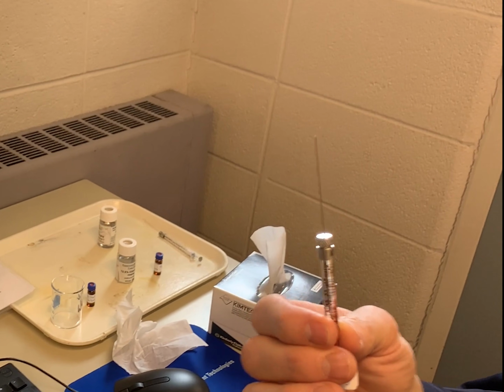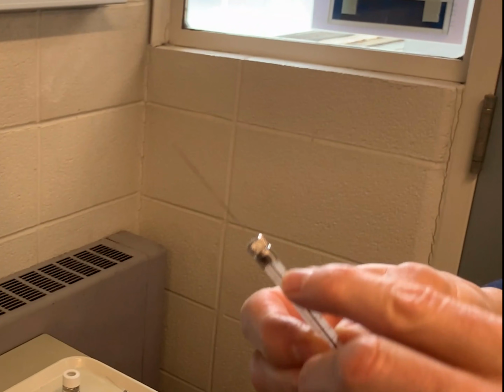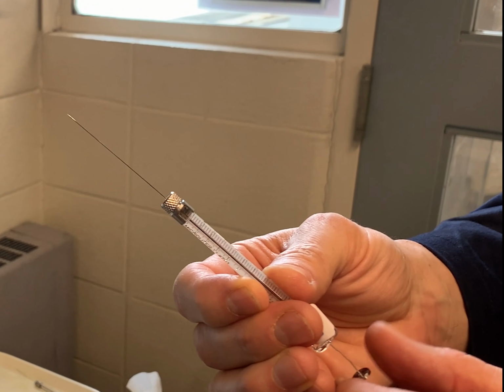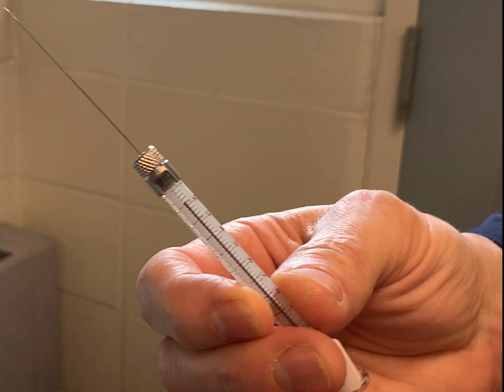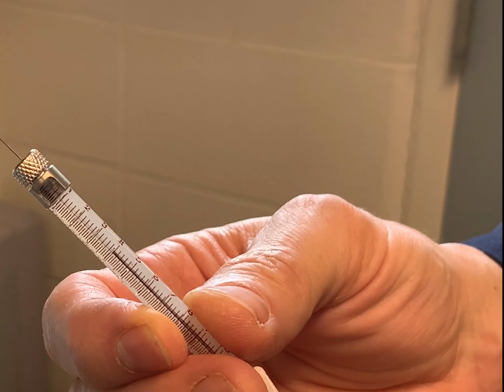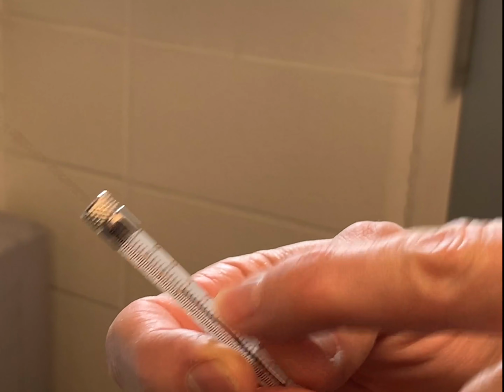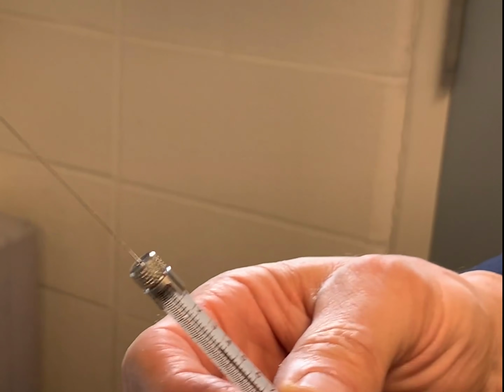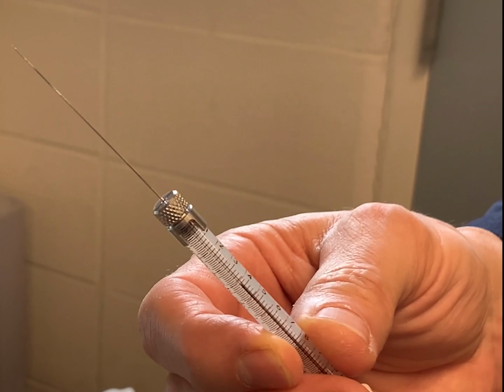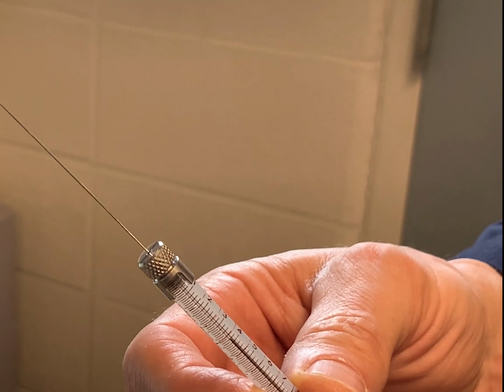Again, if you didn't see those nice sharp peaks, it is usually 90% of the time due to an injection problem. So we talked about the 1 microliter. So you have your 1 microliter. Don't forget your air jacket. So you're going to bring your plunger back 2 to 3 microliters. That gives you that air jacket in here that will take longer to heat up. So your sample is not going to vaporize.